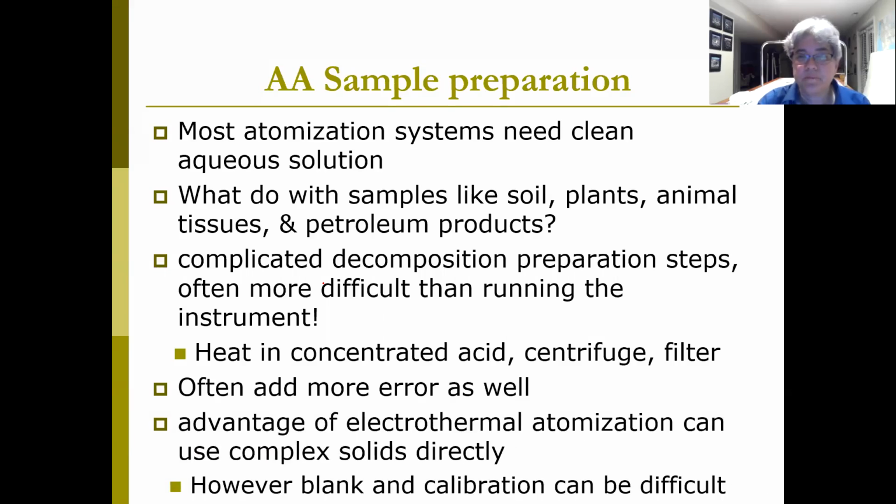So again, that's one advantage of the graphite furnace, the electrothermal, is I can use these dirty samples directly. I don't have to get them cleaned up first. However, getting a blank and calibration can be hard on these complex samples for that.